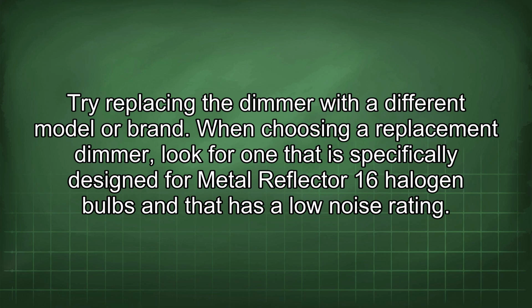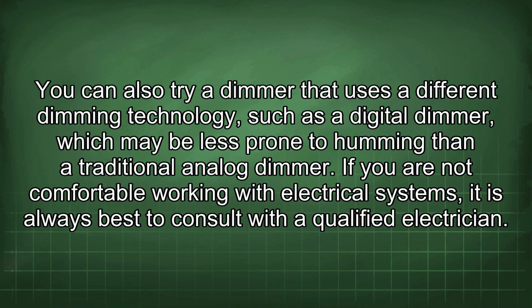When choosing a replacement dimmer, look for one that is specifically designed for metal reflector 16 halogen bulbs and that has a low noise rating. You can also try a dimmer that uses a different dimming technology, such as a digital dimmer, which may be less prone to humming than a traditional analog dimmer. If you are not comfortable working with electrical systems, it is always best to consult with a qualified electrician.